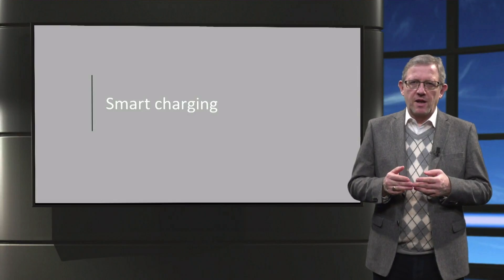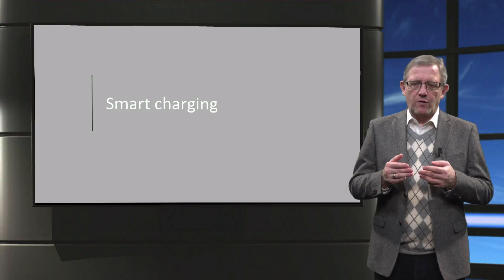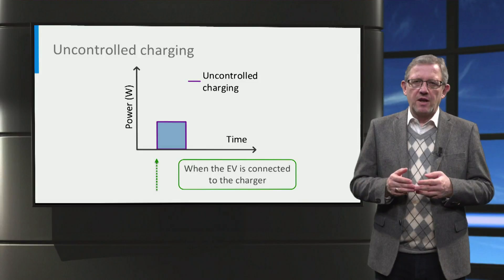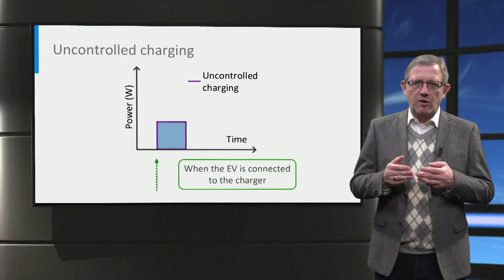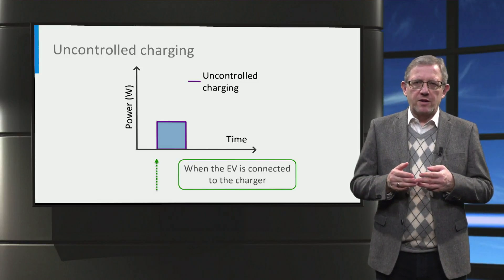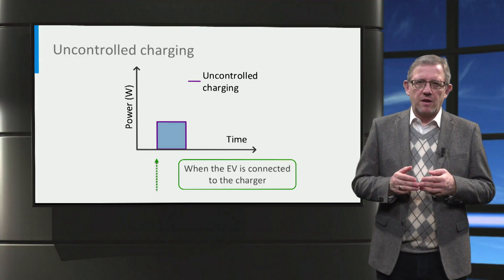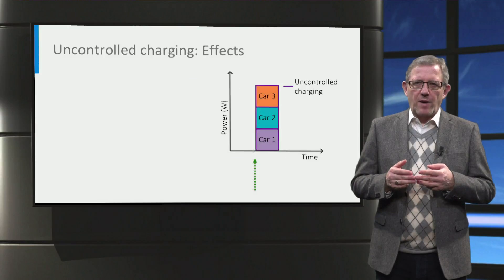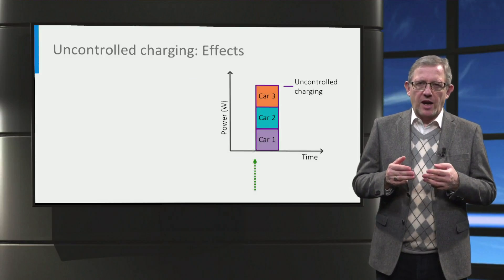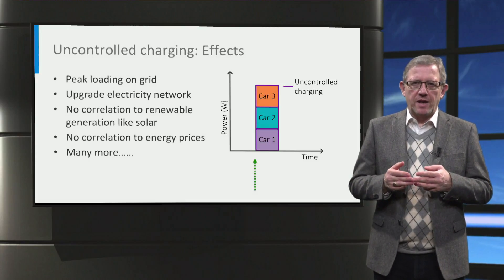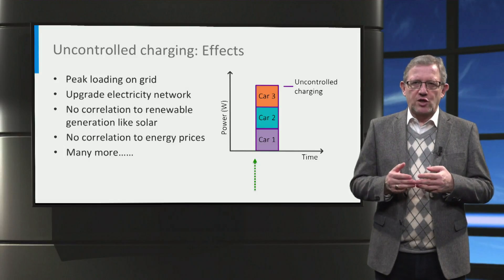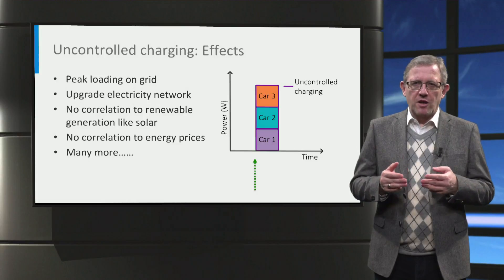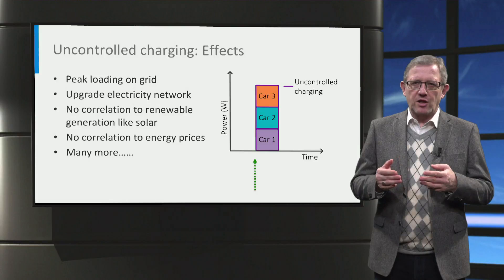Now that we have looked at the charging process, let us see what smart charging is and how it is different from conventional charging. When we connect an electric vehicle to an EV charger, charging starts as soon as the electric vehicle is plugged in. The charging occurs at a fixed charging power until the electric vehicle battery is full. This is often referred to as uncontrolled or conventional charging. In the case of multiple cars connected at the same time, all the cars will charge simultaneously, which may lead to a peak loading on the electricity grid, requiring upgrades to power lines and transformers. Further, this kind of charging has no correlation to renewable energy generation or energy prices, as charging always happens at a fixed power.